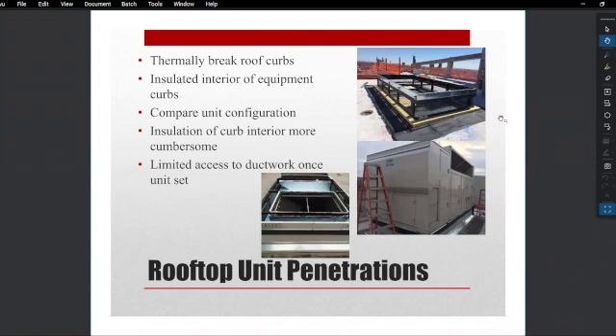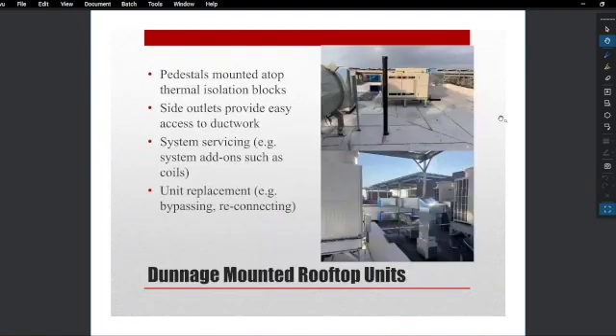So comparing that to a Dunnage mounted rooftop unit on the next page, where we actually utilize a side outlet ERV. This is a lot cleaner for me. With the Dunnage, you only have the Dunnage that's connecting to the roof, so you only need the thermal isolation block there. And then obviously where the roof curb penetrates, you'll also need the thermal blocking under there. And to me, this is a better long-term solution. Also, if that unit ever got changed out or needed to get serviced or replaced, it's pretty easy to not only get the unit on and off, but basically reconfigure the system for a new unit. Before on the rooftop, on the bottom outlet unit, the new unit would basically have to fit or match that duct configuration. And with the side outlet, you can run out your duct and eventually match it to the risers.